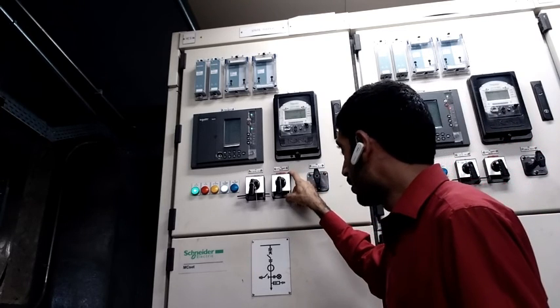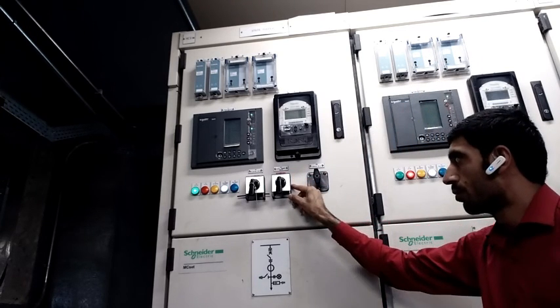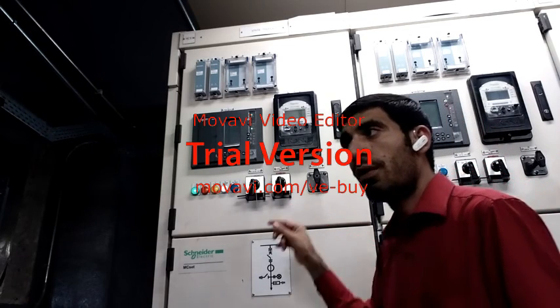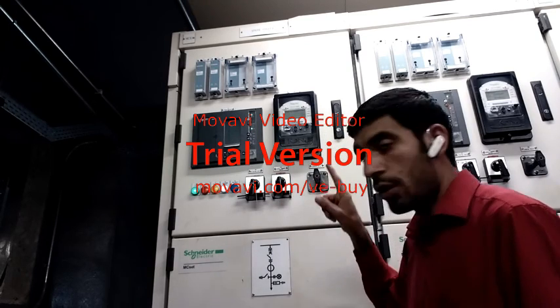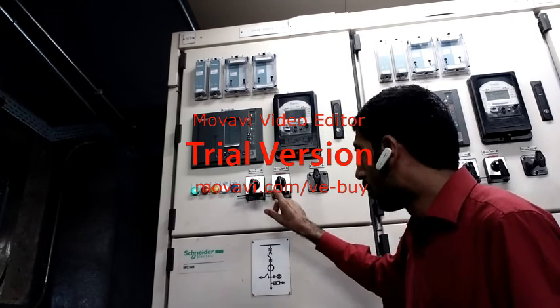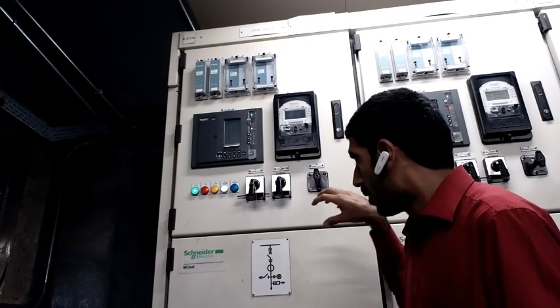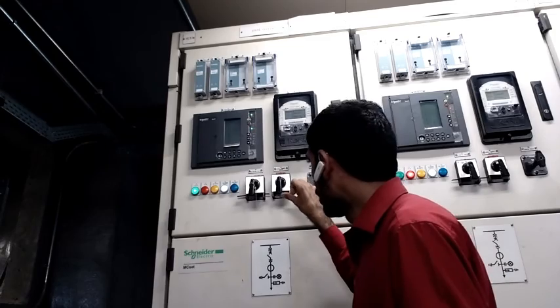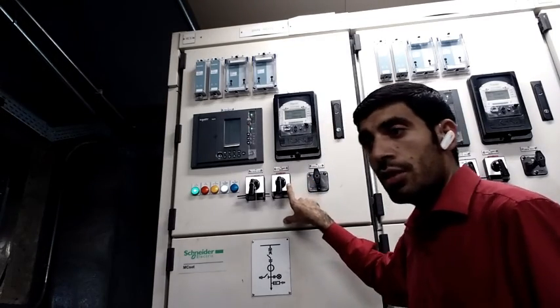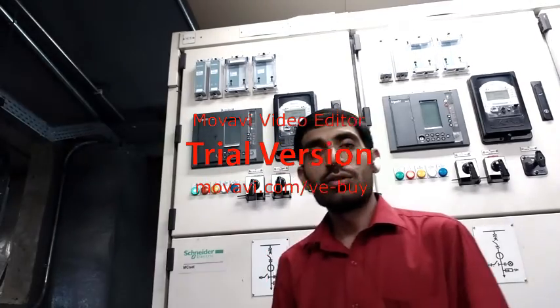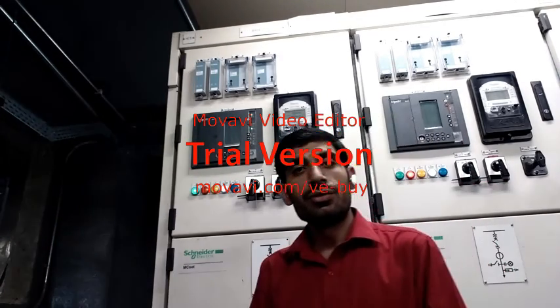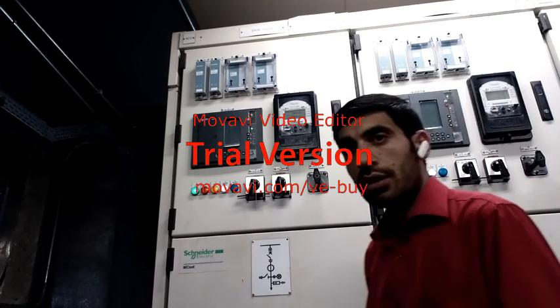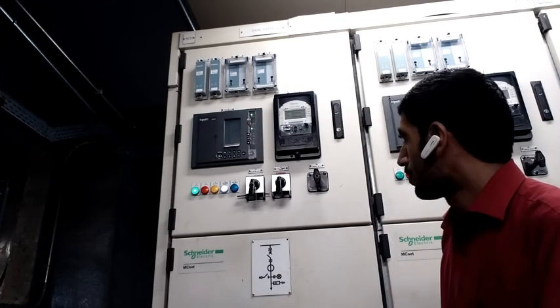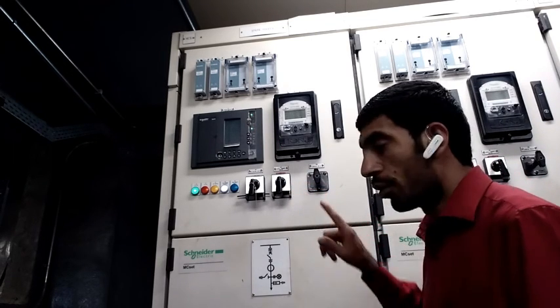And the next thing is the local remote control switch. This local remote control switch is used for two things. One, to manually close the breaker, we put it on local, so we can close and trip the breaker easily here. The other is the remote condition. You can close through DCS, through your signal from the CCB control building. You can close or open the breaker with your signals when you put it in the remote condition.